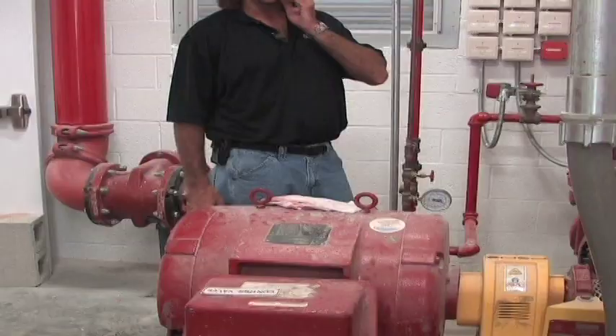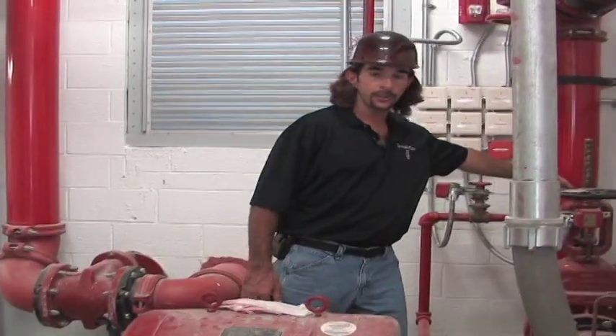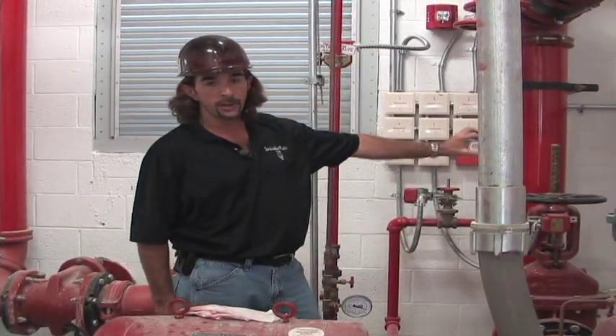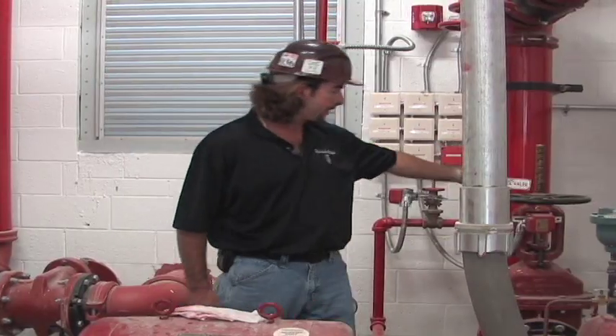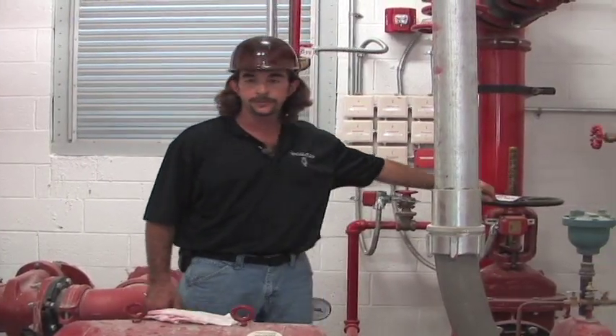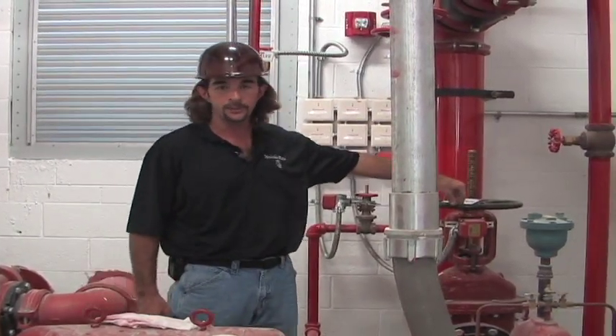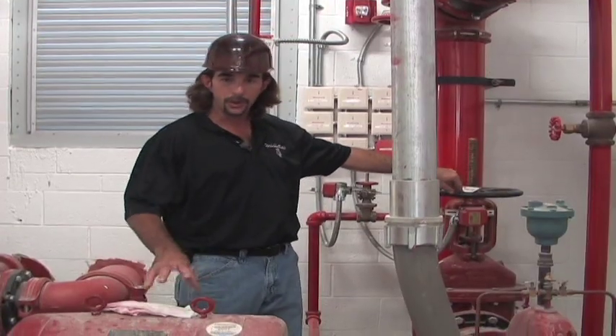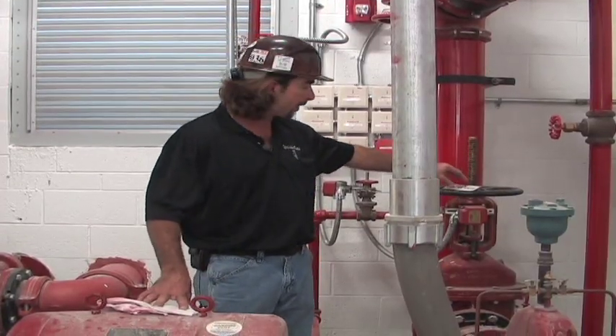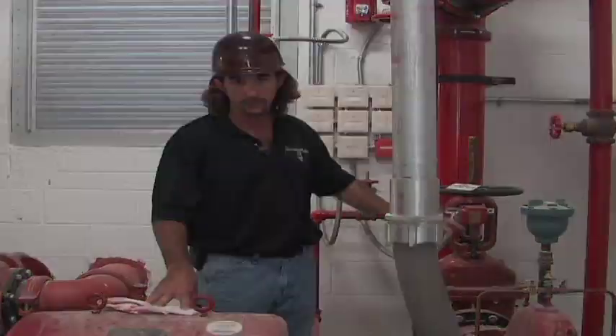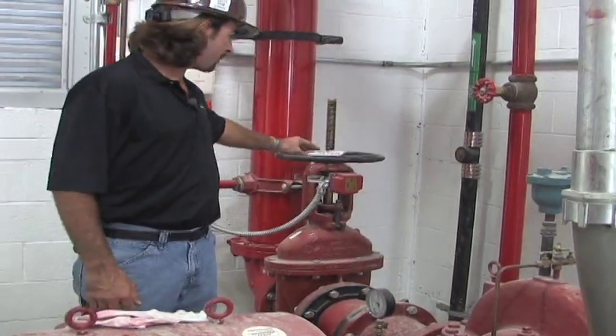Start off our fire pump. We've got our little signage here just so we can actually look at it. This is going to be our supply control valve. This is going to be our main valve for the fire pump, our supply valve coming from the underground. If we had to do any other type of work on this, this would be our valve that would shut the water off to the fire pump. So we do have our supply control valve.